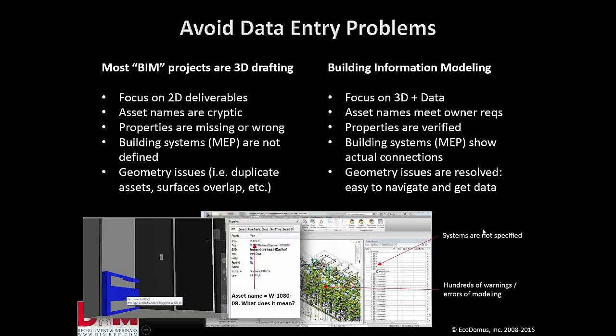The challenges that you're going to have definitely is with the quality. Most of the modelers are still drafting using the BIM authoring tools instead of modeling. Modeling built MEP systems is the biggest culprit. There's a lot of problems with MEP systems modeling. Properties, everybody is loading whatever properties they see, even though those properties don't really bring any value to the owner. Sometimes you have an air handling unit that has 50 attributes, and all of those 50 attributes are related to the geometry of the air handling unit instead of actually having the operational values. But the owner looks at it and says, oh, wonderful, 50 attributes, that's so cool. In reality, what's the point? So that's the challenge that you're going to be having, and we're helping our clients really to figure out how to clean those things and how to avoid the problems.